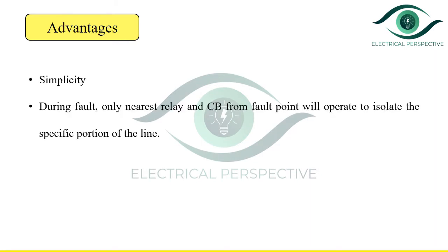The advantages of this system are: firstly, it is a very simple system. Secondly, during a fault, only the nearest relay and circuit breaker from the fault point will operate to isolate the specific portion of the line. This selectivity is achieved because of the time grading.